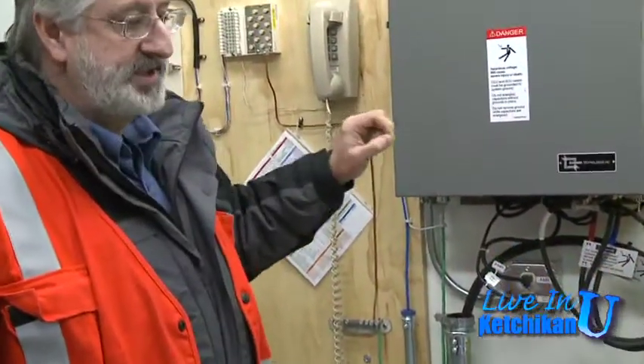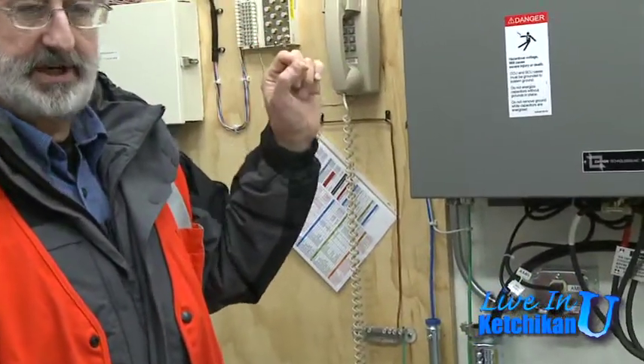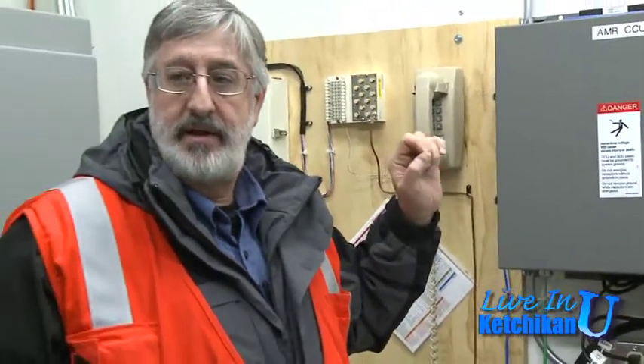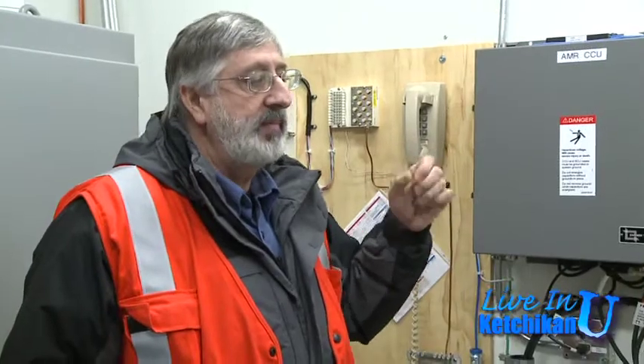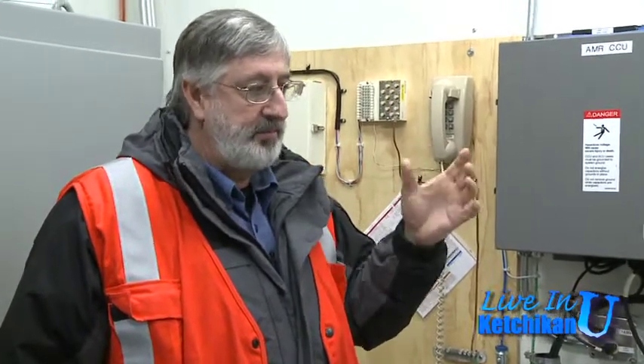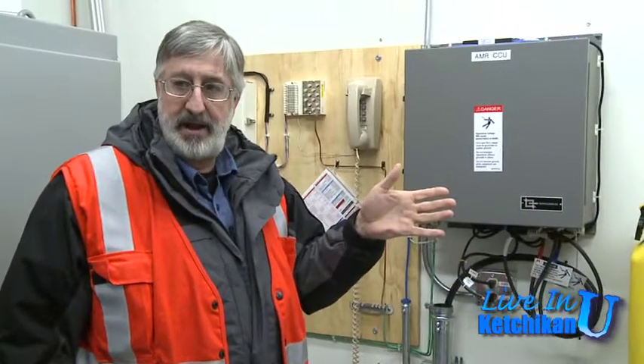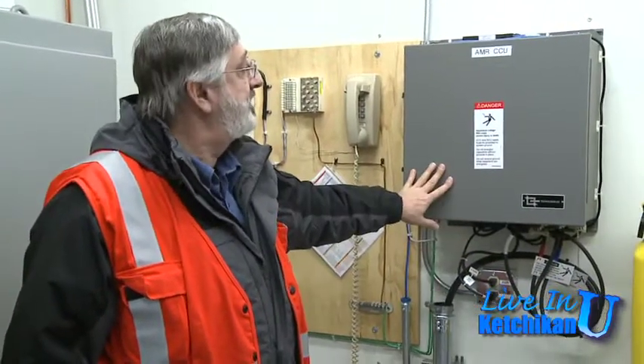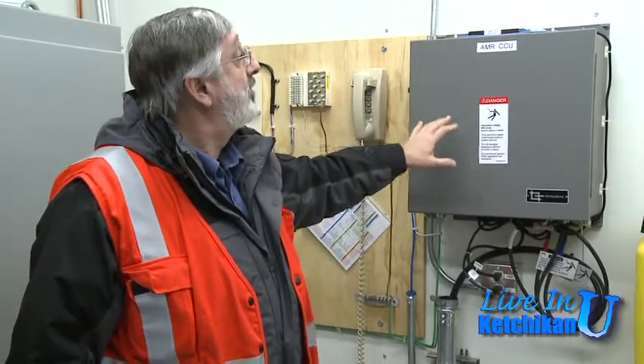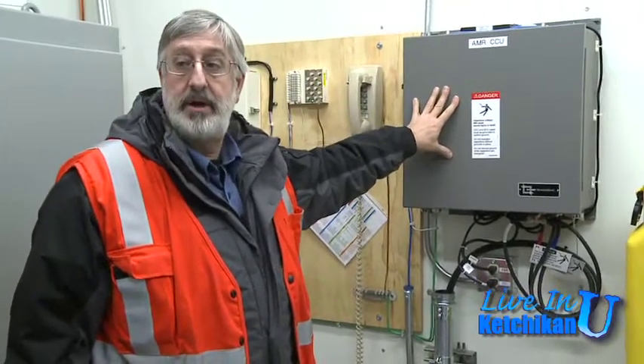It actually puts a small digital signal on the voltage going out, and that digital signal is picked up by the meter on your house, telling it when it's being pulled. Then there's an exchange of information: the meter puts its data out on the line, and this picks it up. So the AMR is automatic meter reading.